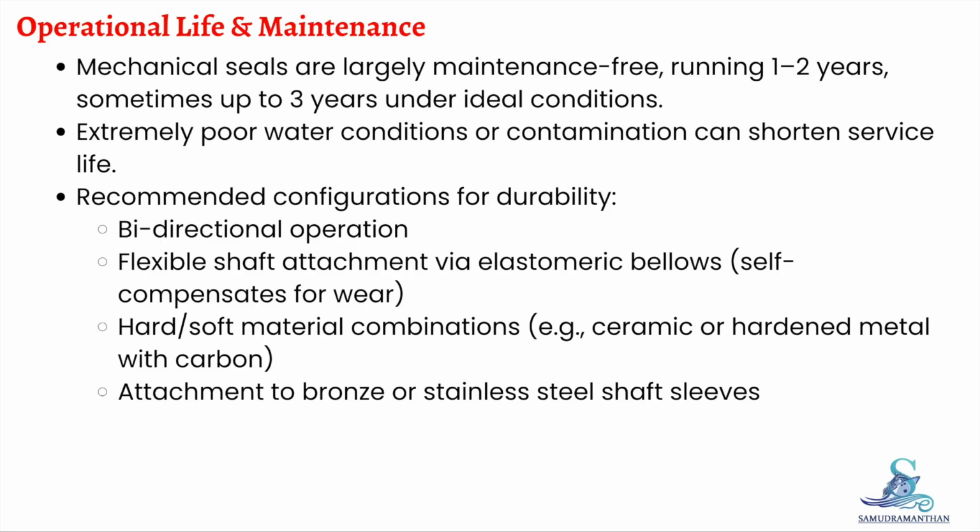Recommended mechanical seal configurations include bidirectional operation for flexible flow conditions, elastomeric bellows to automatically compensate for seal face wear, hard-soft material combinations, ceramic or hardened metal with carbon for optimal lubrication, attachment to bronze or stainless steel shaft sleeves for durability.